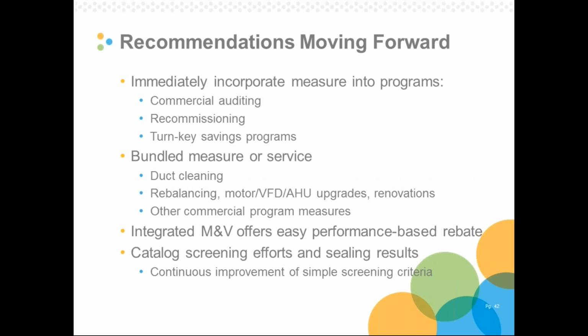Recommendations for moving forward. Basically, we need to immediately incorporate at least duct sealing screening into existing programs. It's very easy to do, and it should, as of today, be considered in commercial auditing, recommissioning, and turnkey savings programs. Duct sealing also makes sense as a bundled measure or service, and this includes for energy efficiency and non-energy efficiency reasons. It goes nicely with duct cleaning, any kind of rebalancing work, motor, VFD, or air handler upgrades, and any kind of renovations. As a side note, a lot of the systems we visited in this project were changed significantly over their lifetime, and those would have been perfect opportunities to update the duct system and reduce leakage. And it could also be added with other commercial program savings measures.